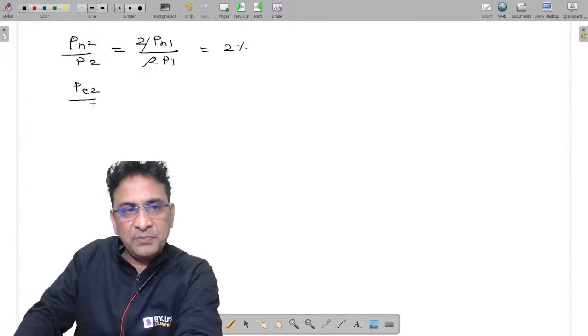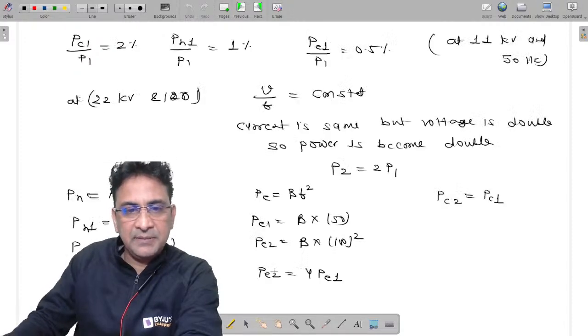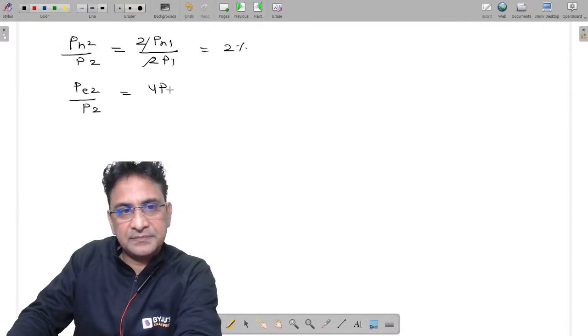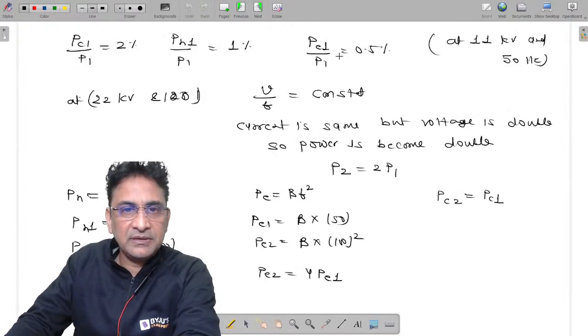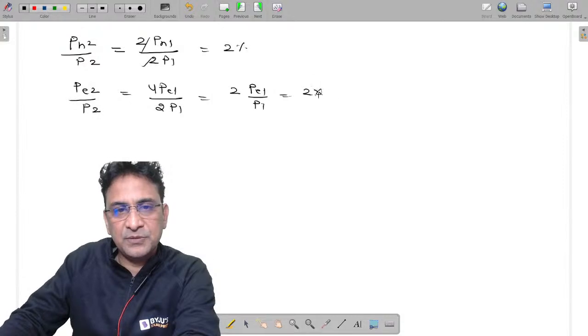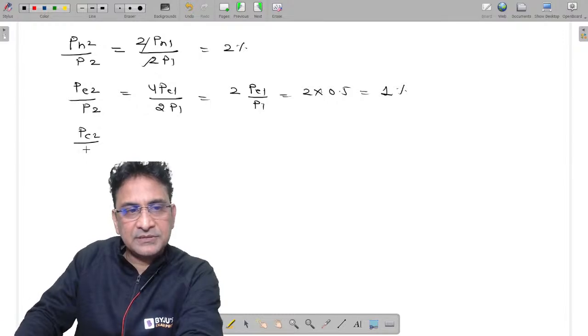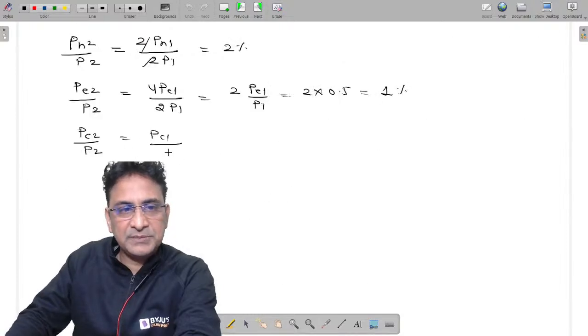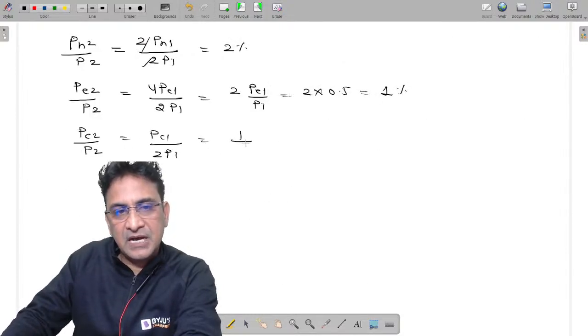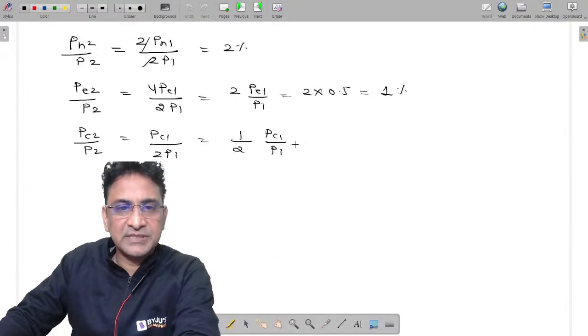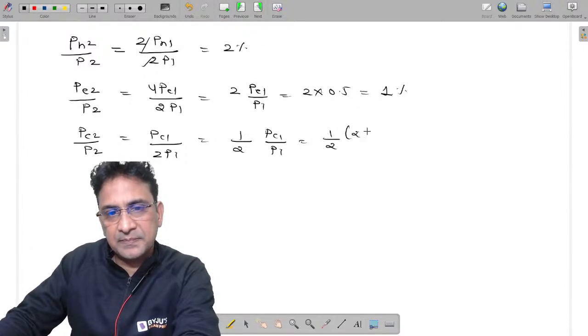Similarly, PE2 upon P2, total eddy current losses, PE2 is the 4 times of PE1 and P2 is the 2 times of P1. So it is become 2 into PE1 upon P1, and PE1 upon P1 is the 0.5%. So it is become 2 into 0.5. So it is again 1%. Now the copper loss, the PC2 is the same as the PC1, but P2 is become 2 times of P1. So it is the half of the PC1 upon P1. And the PC1 upon P1 was the 2%. So it is become 1%.